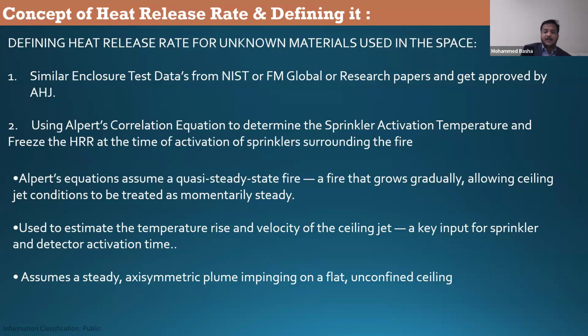So what are we trying to do here? We are going to see what is the activation temperature of a sprinkler in a particular space. Then based on this, what will be the growth rate of the fire at the time of sprinkler activation? Because normally, why are we providing sprinklers? To control the fire, right? Sometimes it will extinguish as well. So when you start to control the fire, what happens? Your HRR will not continue to grow further. It will decay down because of the cooling effect of the sprinkler. So this is a good point, that the HRR value corresponding to the sprinkler activation time can be used to define the smoke management system calculations. This is called Alpert's correlation.